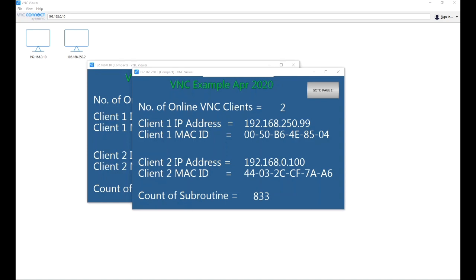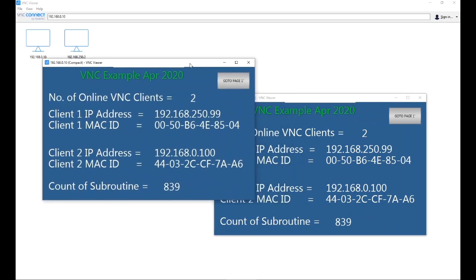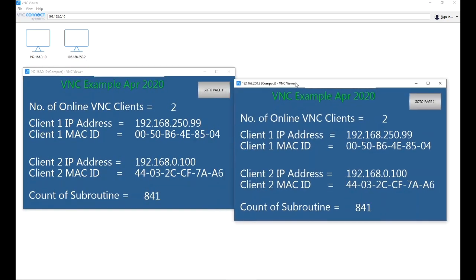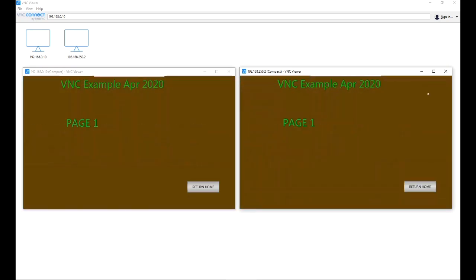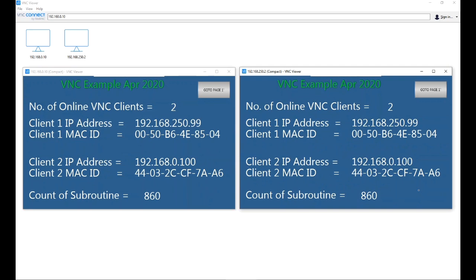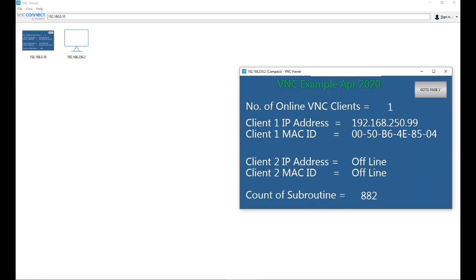Here's both my IP addresses shown and the MAC addresses shown. So both connections are currently online, and we could have more connections made. Of course if you enable the whitelist, you have the MAC address and the IP address of the client that's coming online. So both screens will operate the HMI remotely. As I said earlier, be warned on this. Obviously it's a view and operate, but one could use the IP and MAC address from a unique user to identify what sort of level of control or monitoring or recipe control you could use within the HMI. If I take one offline, you can see the other one now tells me I've dropped to one client. The other's gone offline.